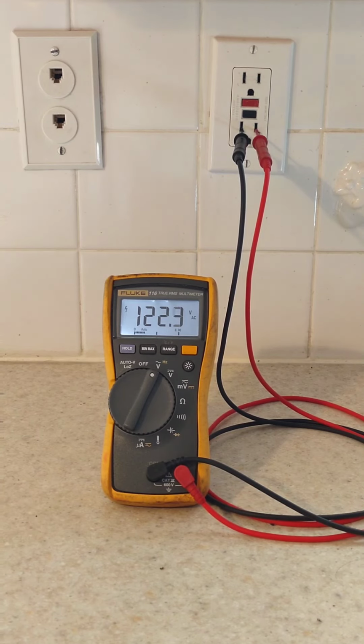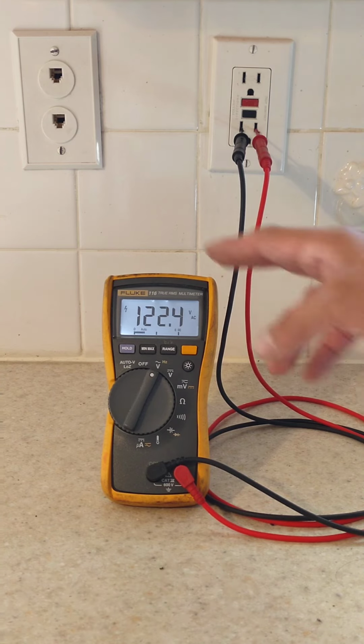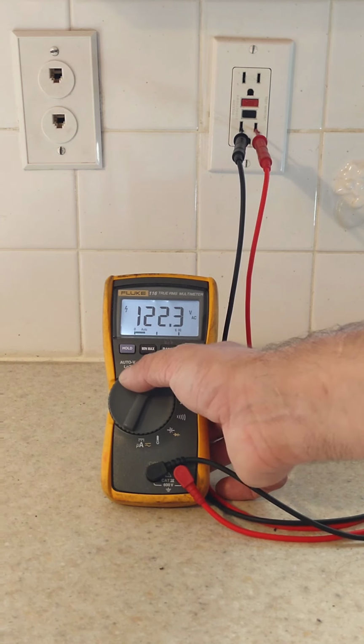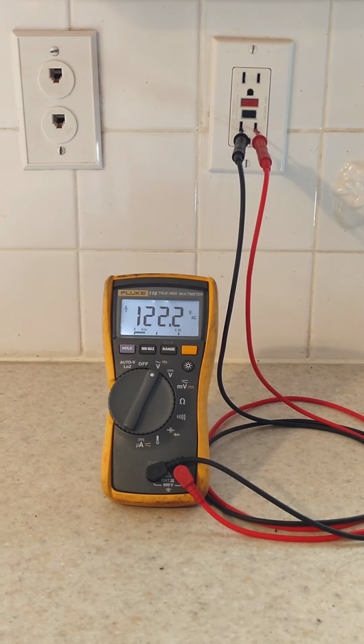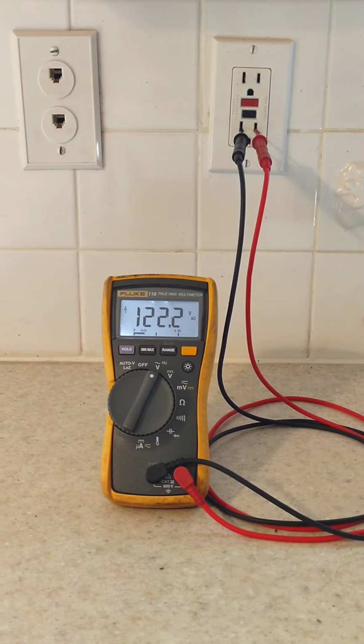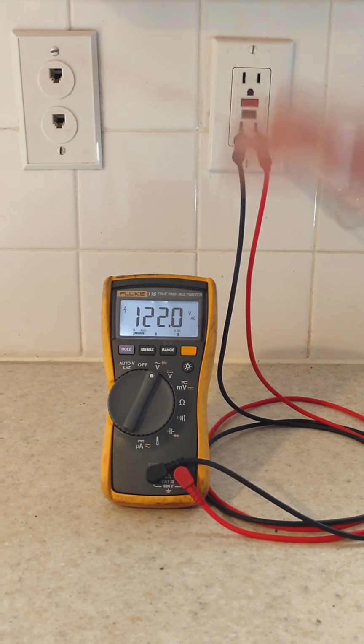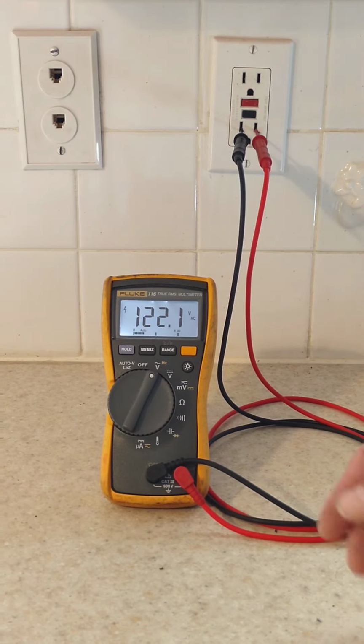Another easy way to know if you're seeing a ghost voltage or a real usable voltage, some higher quality multimeters will have what they call a low Z function. Z is the symbol they use for impedance, which is, for these purposes, almost the same thing as resistance. It's presenting more of a load, it's drawing more current from the outlet to bleed down that ghost voltage and tell us if there's actual usable voltage there or if it's just a measurement artifact.